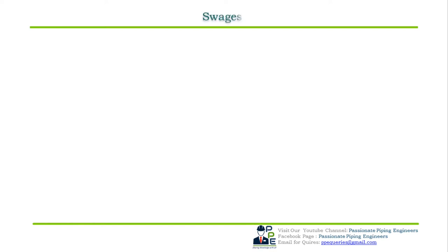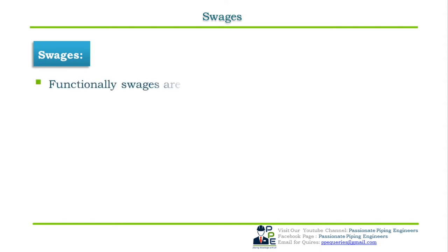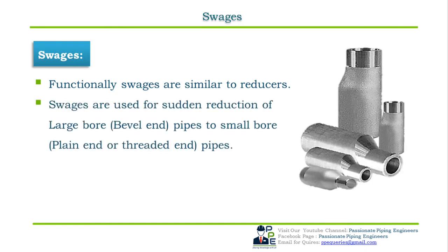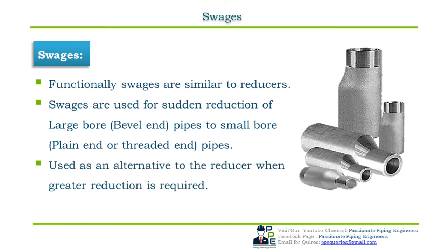The next fitting used for joining two different pipe sizes is the swedge (or swedge nipple). Like reducers, swedges are used for reducing line sizes, but reducers have limitations: reductions are available only up to half of the larger diameter. Swedges are used for sudden reduction in line sizes — joining large bore or beveled-ended pipe to small bore plain-ended or threaded pipe. They are an alternative to reducers when greater reductions are required.